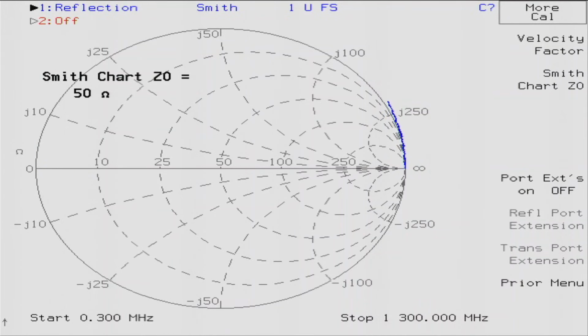All right, so let's take a look at my self-made calibration standard, okay? And I'm going to put in that short. All right. So this short, we're showing a very big line over on the left-hand edge. It's not a point where the short's supposed to be. And that's because we've calibrated at one plane, but we're measuring at a different plane, and we're seeing the inductance of that trace as a line. We're getting, it's not inductance, it's electrical length. It's rotating in the clockwise direction.